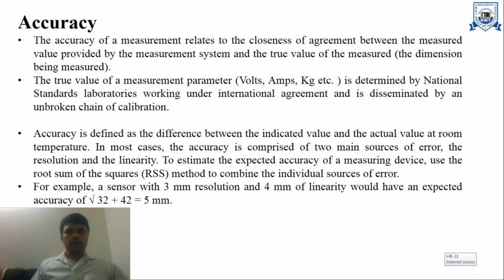Accuracy is defined as the difference between the indicated value and the actual value at room temperature. In most cases, the accuracy is comprised of two main sources of error, the resolution and the linearity. To estimate the expected accuracy of a measuring device, use the root sum of squares (RSS) method to combine the individual sources of error. For example, a sensor with 3 mm resolution and 4 mm linearity would have an expected accuracy of 5 mm as given by the root sum of squares method.